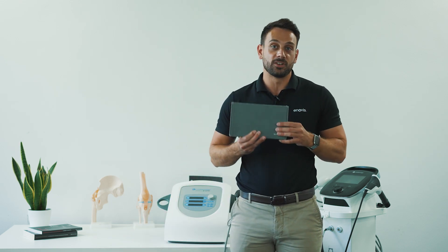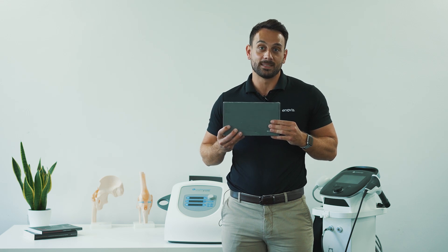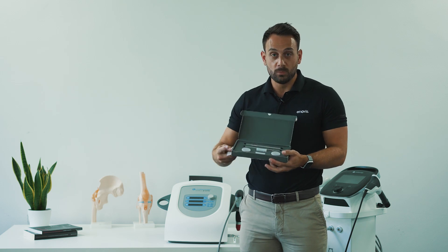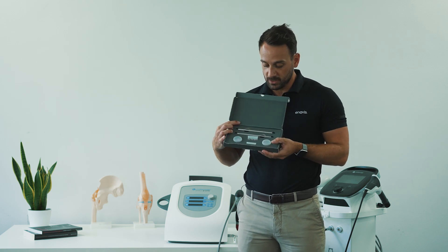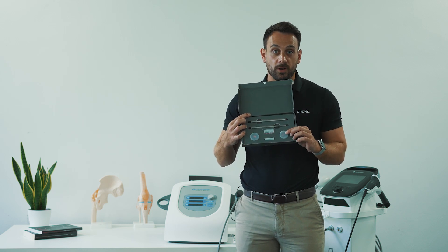The first thing that you'll need is the revision kit. There's a link in the description below where you can order these, or you can speak to your local Enovis contact. Included within your revision kit are parts for 2 million pulses, or two revisions. You have two guide tubes, two projectiles, and two pots of O-rings.